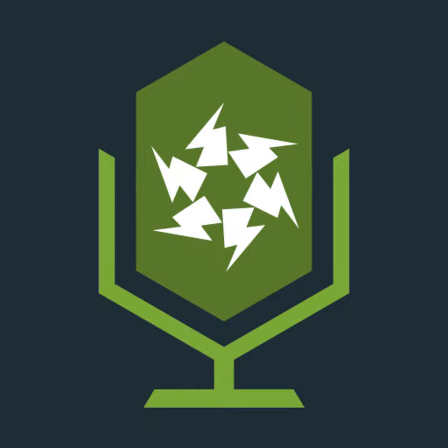So that's the new factor, 44 over 0.705. And what we're going to end up with is the 44 going up to a new value, and it's going to be 62.4. So we get IT is equal to 62.4. So let's call it 63 amp. Okay, now it's IT. This is a tabulated value. What we now need to do is go and select an IZ with that IT. So we need to go and get that.